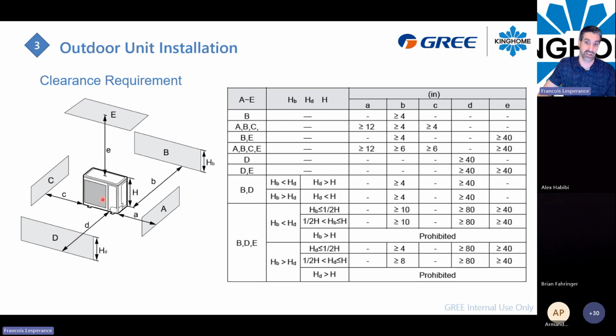It's that long because we don't want the unit to push the air out of the condensing unit and get it back, so the unit would always recycle the same air. By having 40 inches in front of the unit, we make sure the air passing through the outdoor unit will be pushed away and will not recycle the same air in the space, because that will cause you some problems over time if the unit recycles the same air again and again and again.